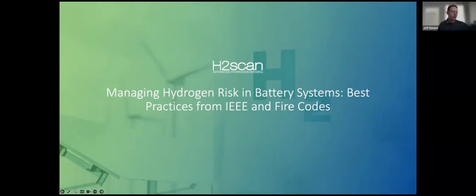Okay, so basically the hydrogen systems, we recommend that the threshold set points are set at 1% and 2%, and then also there's a fail alarm. So basically what that means is that at 1% hydrogen, you should have a plan that activates either an exhaust fan, or you can even do some manual evacuation of the hydrogen in the space. So at 1%, it's very safe to go in and actually deal with it.